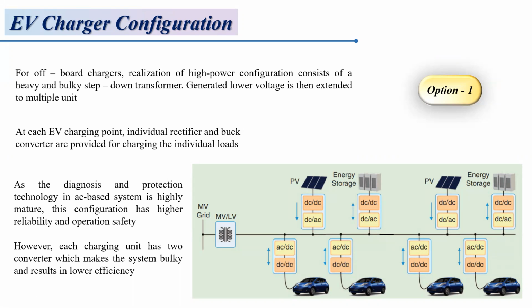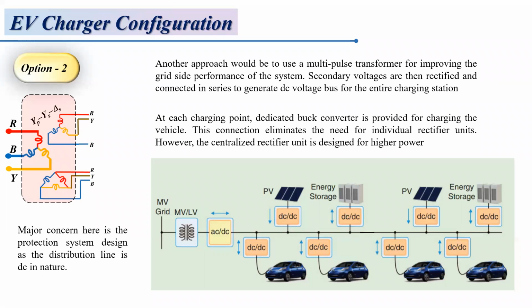The next thing is distributing the power using a DC link. As you can see, after the transformer we have a central rectifier which gives power to all the units. Compared to the previous topology, here fewer converters are used. However, the major concern is the protection of the DC line.